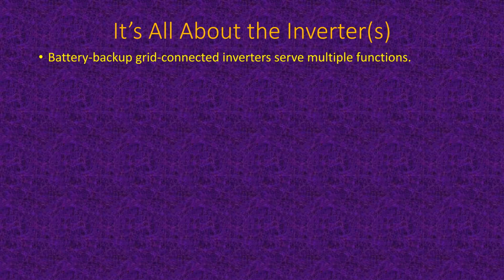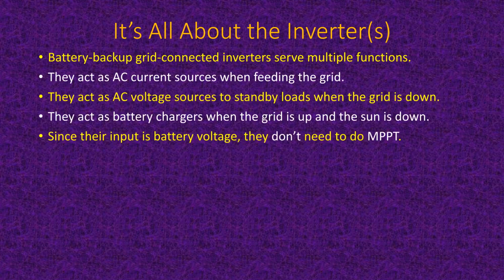So when we have a slide that's kind of busy with a lot of words on it, generally that leads to a slide that has pictures. And so the key here for any kind of IEEE 1547 compliant inverter, and that could be for low-head hydro, for wind, small windmills, or solar, and we're going to be most specifically talking about solar today, is that these units act as alternating current sources, or AC current sources, when they feed the grid. And the reason for that is they use the grid voltage to stabilize the frequency of the current that they generate. In this way, if the grid voltage is lost, the current loses its synchronizing signal, it goes off frequency, the inverter notices that and shuts down.